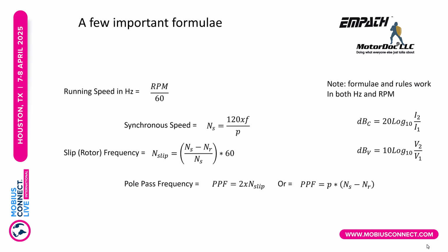Now, if I'm looking at my decibels, which we do decibels versus inches per second or millimeters per second or whatever, it's 20 log 10 of the current of interest divided by the primary current, meaning the current at line frequency. Why is this important? Well, as my load varies, my current varies. So that means that if my primary current is varying, my defect current is also going to vary, and it ends up being that I will only have a change of 1 to 3 dB depending on the type of fault based on load. So I can look at a no-load machine, see a defect, and it's going to be about the same as if I fully load the machine in most instances. There's special cases, and that's part of what we would do for troubleshooting where that's not the case.